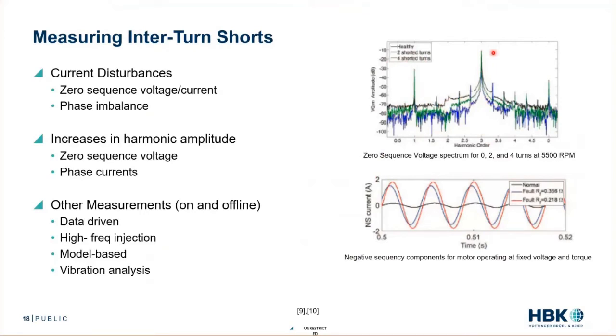We have some really good indicators and multiple indicators that show us a failure is happening. And if we have enough of these, we can start to identify why that failure is happening and where that failure is happening. This might tell me I have a turn-to-turn short. This and this might tell me I have a turn-to-turn short in phase one.